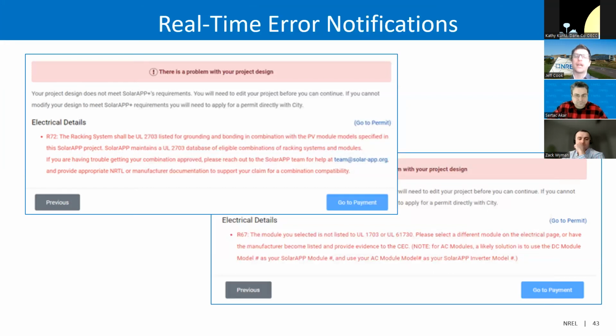meaning the module and the rack were not tested together for grounding and bonding. And that needs to be shown in the installation manual, that the module and the rack were tested together. That is a common error. A lot of jurisdictions don't check for it, but it is required per the code that they are tested as a system to 2703. SolarAPP checks that every time, and it will fail the contractor and say, this project is not approvable. You have to go back and change your rack or your module to have a compliant combination. And so we reject them. So no project can go through SolarAPP without being code compliant.